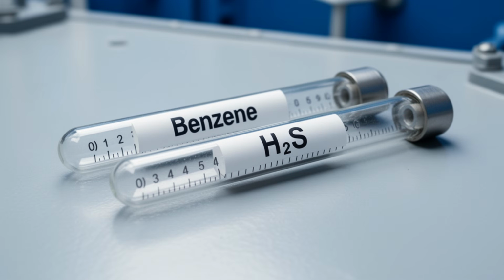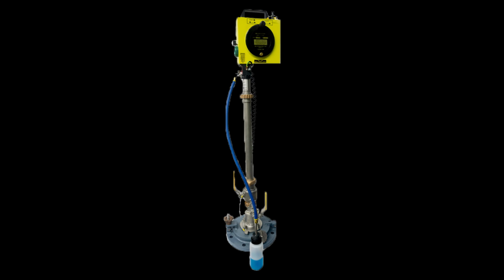Vessel operators must define the toxic gases relevant to your specific cargo and provide the right tools to measure them. Check that your tubes are correct for the current cargo. Using a generic tube for a specific toxic gas may not be sufficient. If equipment for restricted or closed sampling is missing or defective, it will lead to a negative finding.